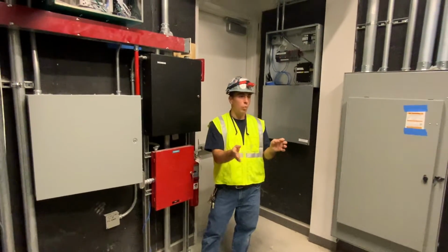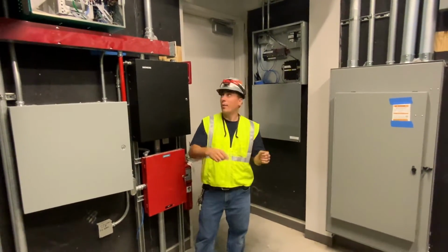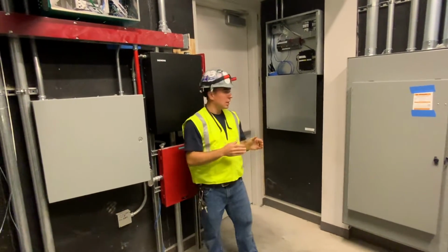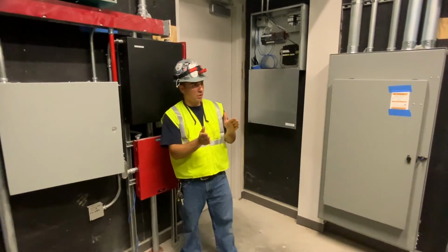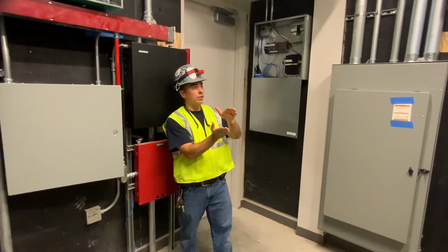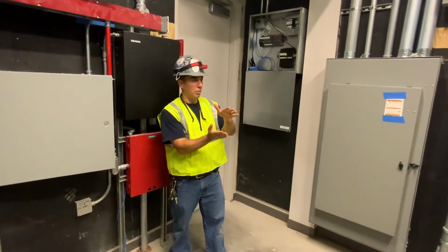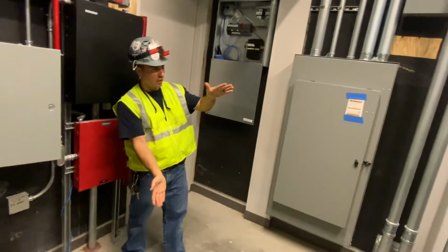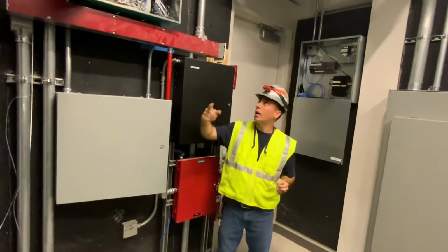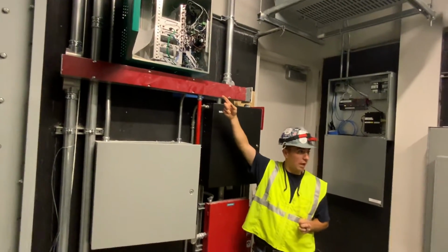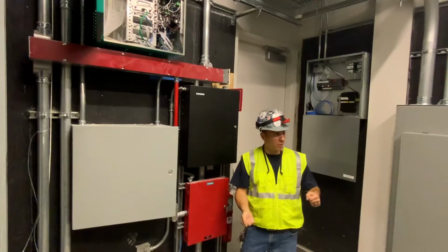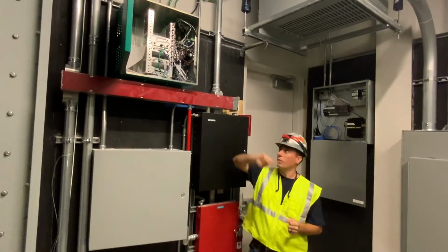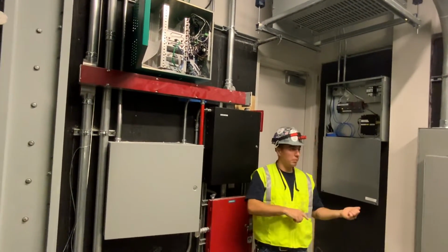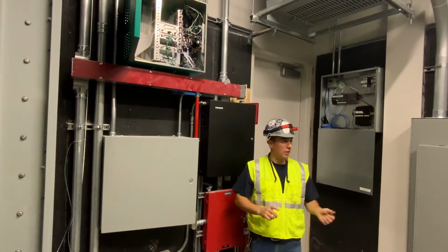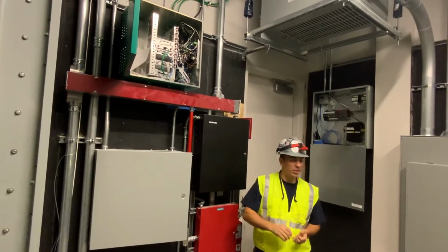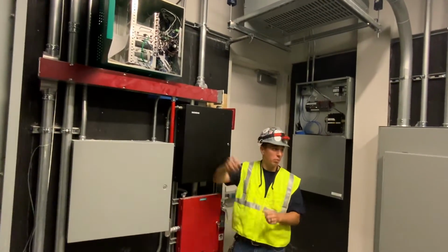So one of the advantages to doing it that way and having it all go through the same sensors is if you ever start to get a sensor drift, the reference and the space are both drifting the same. You will never have them drifting differently. And then every 6 months we come out and we replace these sensors with calibrated sensors. We get sensors shipped out from the factory that are calibrated, plug them in here, ship back the old ones for them to get recalibrated. So they're constantly getting recalibrated. So all the sensors are here. Everything else is just a sample point.